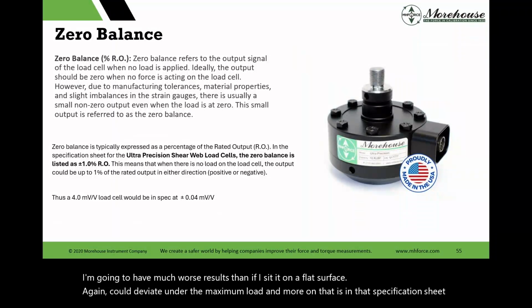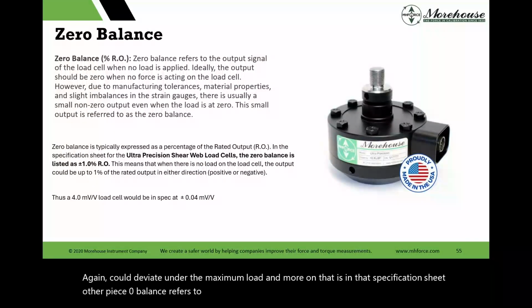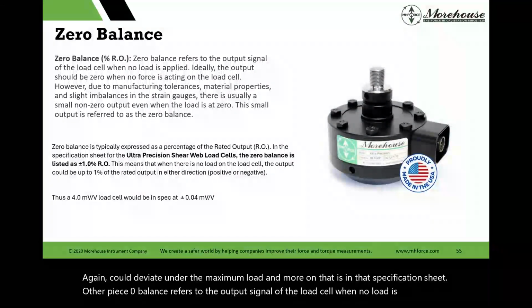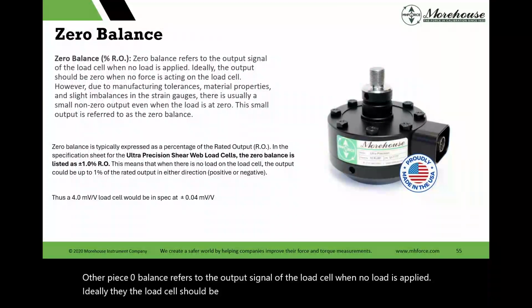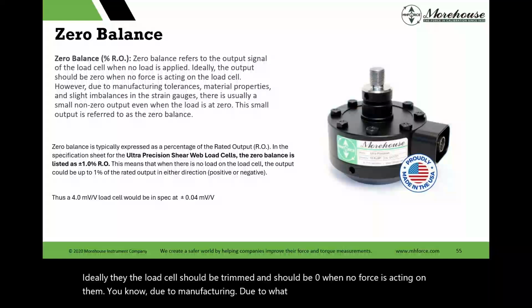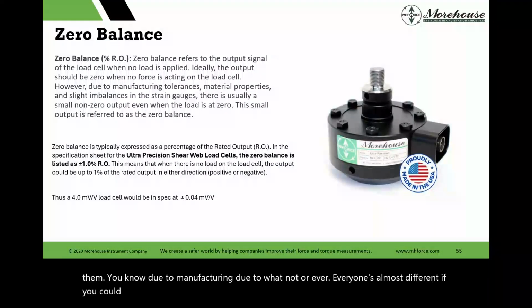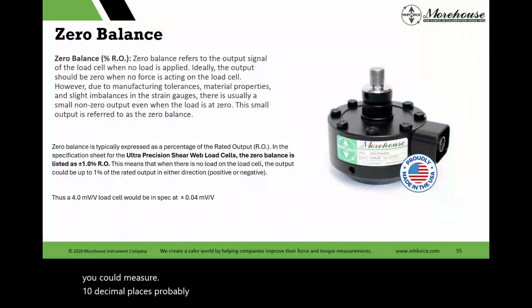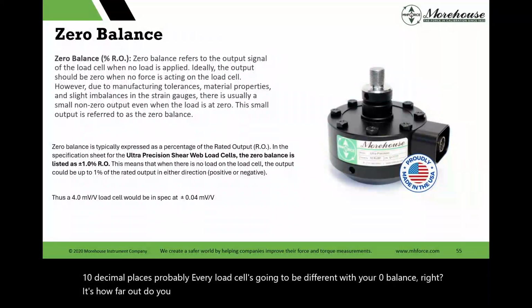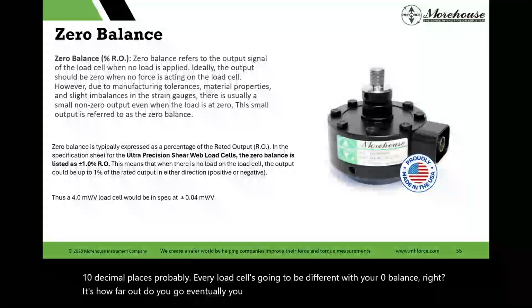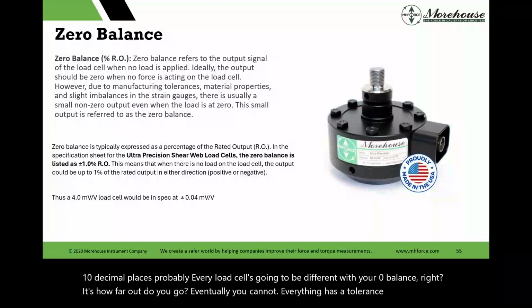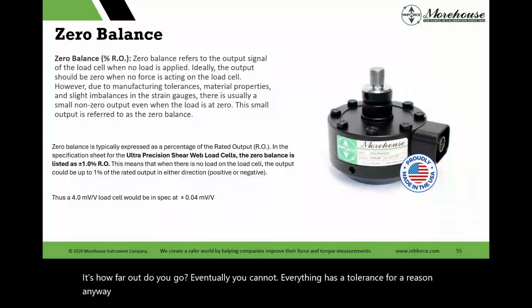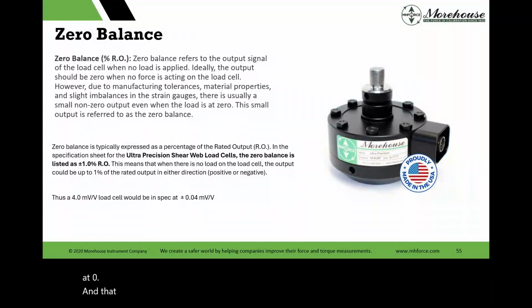Other piece, zero balance, refers to the output signal of the load cell when no load is applied. Ideally, the load cell should be trimmed and should be zero when no force is acting on it. Due to manufacturing and whatnot, everyone's almost different. If you could measure 10 decimal places, probably every load cell is going to be different with your zero balance, right? It's how far out do you go? Eventually, you cannot; everything has a tolerance for a reason. Anyway, so imbalances in the strain gauge, there is usually a small non-zero output when the load is at zero, and that small output is referred to as zero balance.